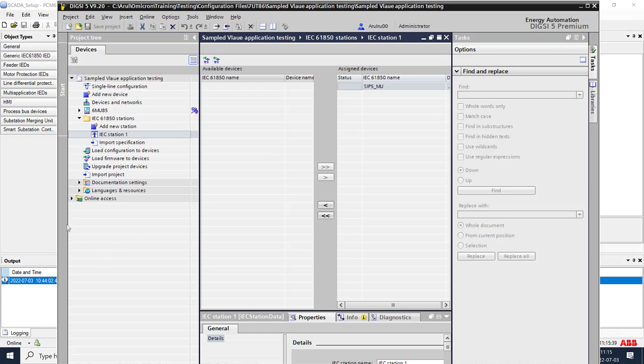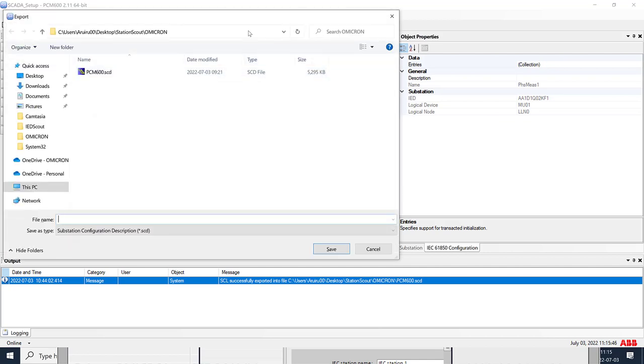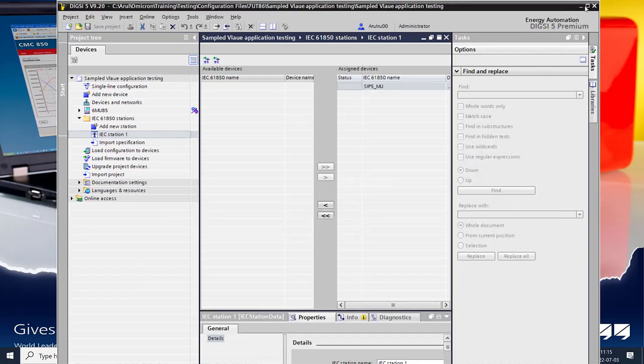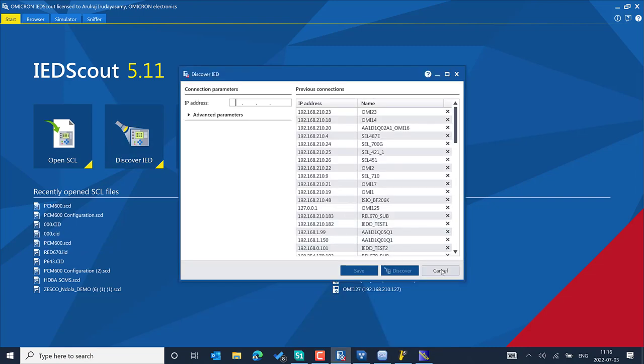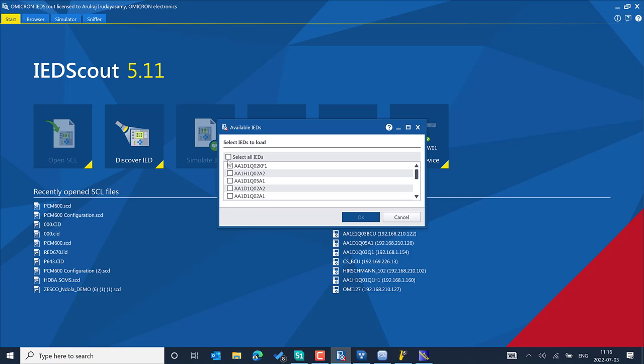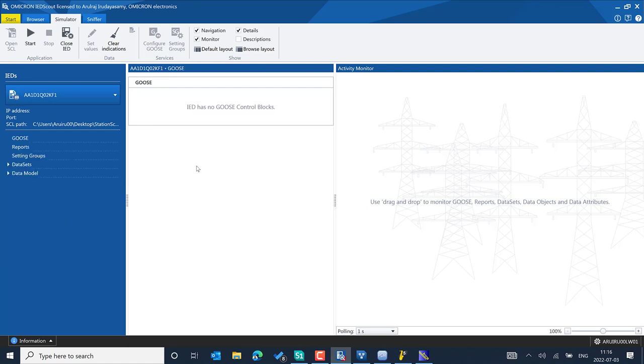In our case, we already exported one of the SCL files from PCM600. You can find it under the StationScout folder. Go to Simulate IED, provide a path, and pick the SCL file you exported. You can import all IEDs and choose them one by one, or import more than one SCL file for flexible simulation.